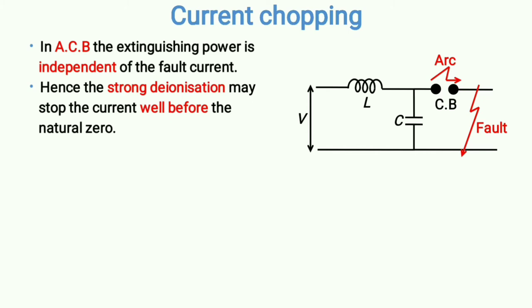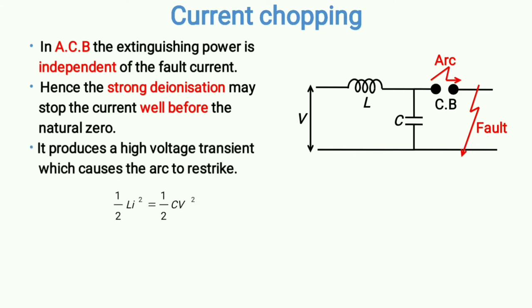Here, however, the arc current or fault current is forcefully stopped well before the natural zero, which creates a huge transient and huge energy dissipation. It produces a high voltage transient which causes the arc to restrike. At natural zero, the change in current (di/dt) is not very large because near natural zero the current is almost going to zero.